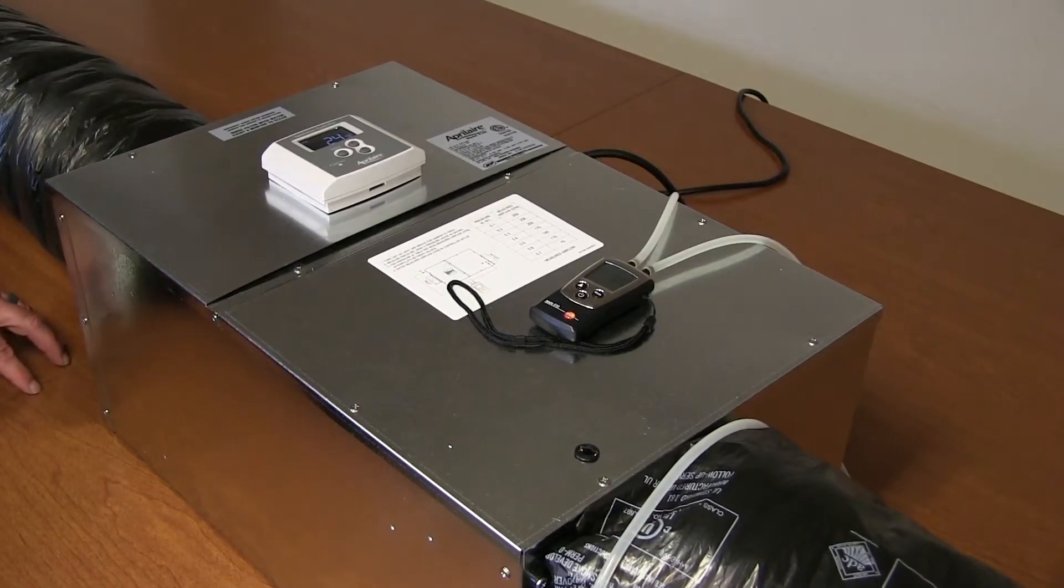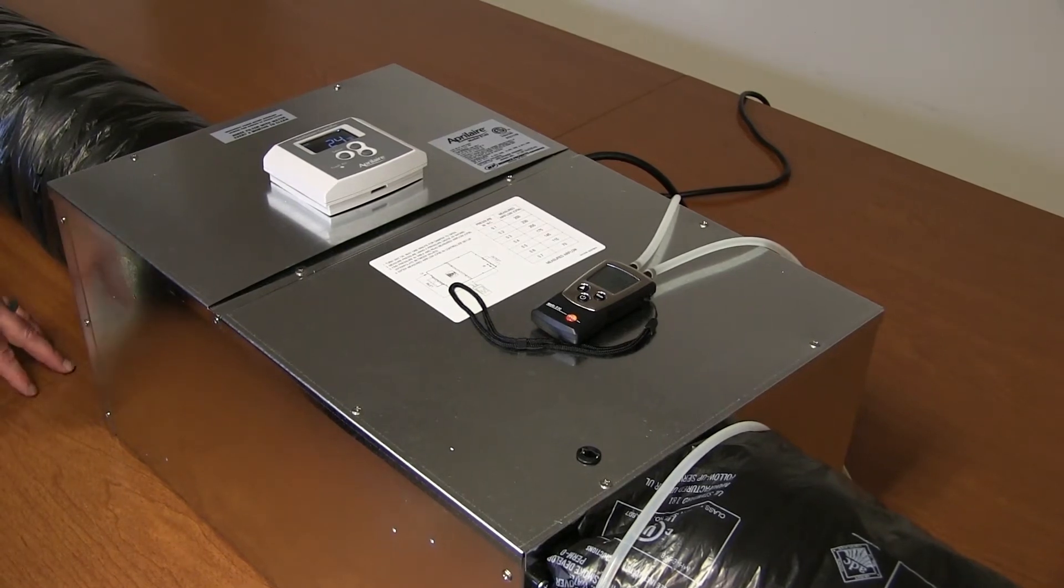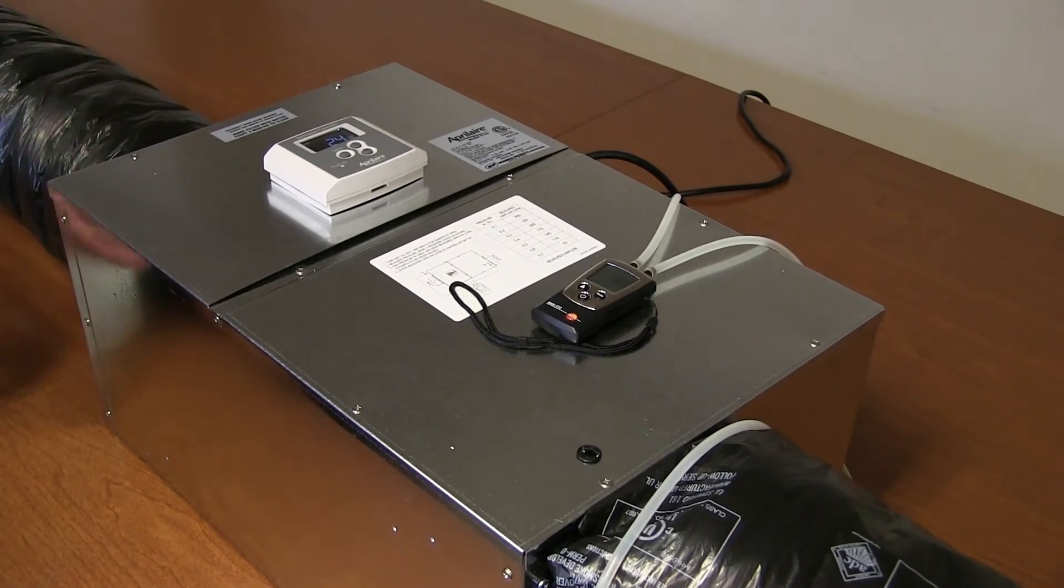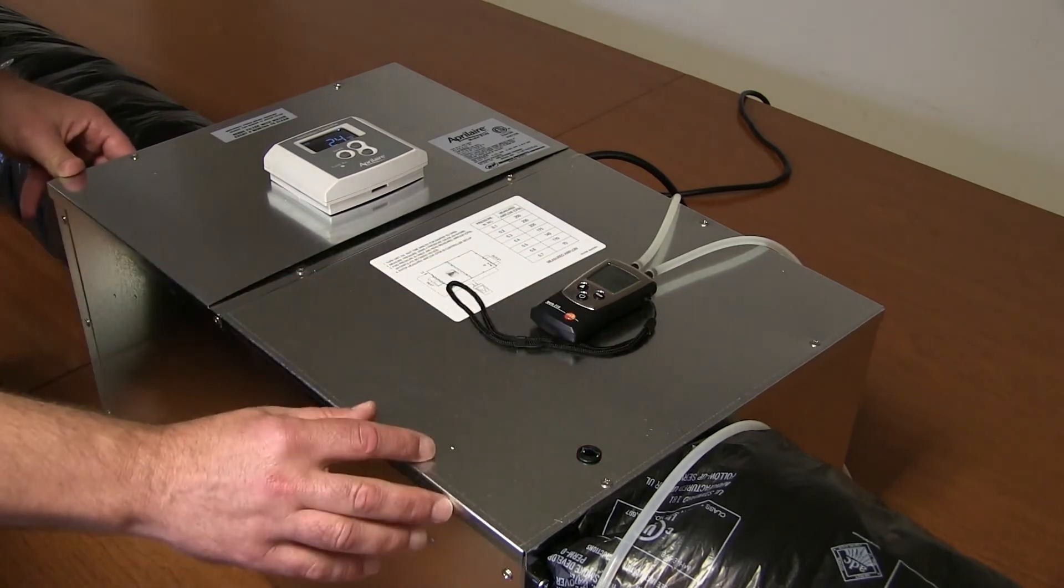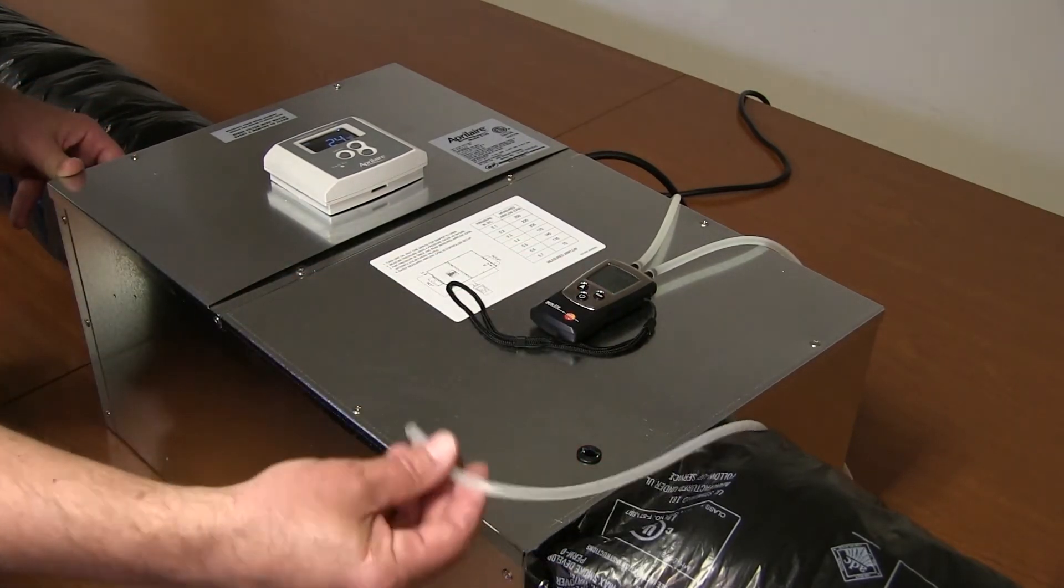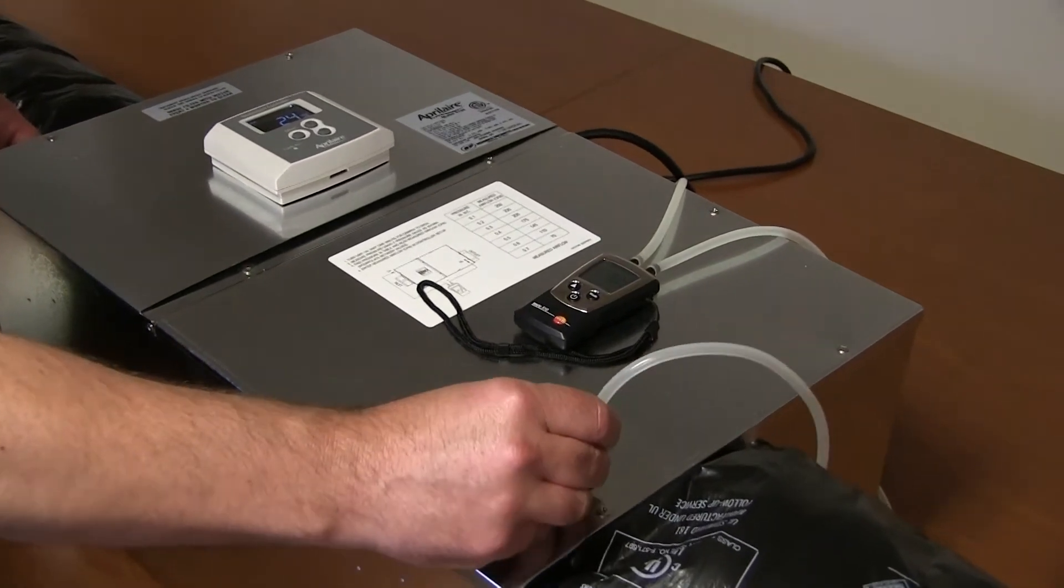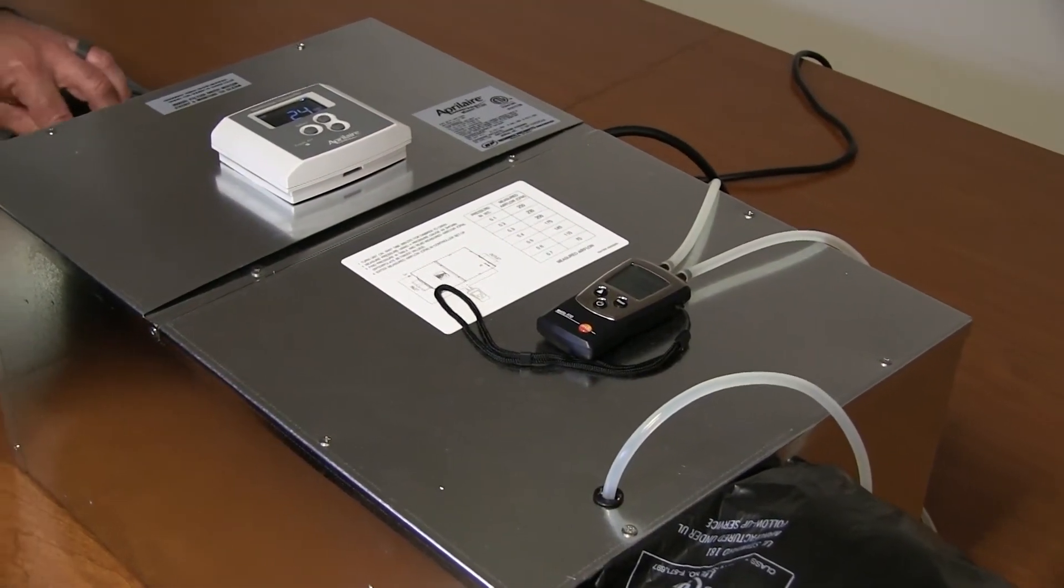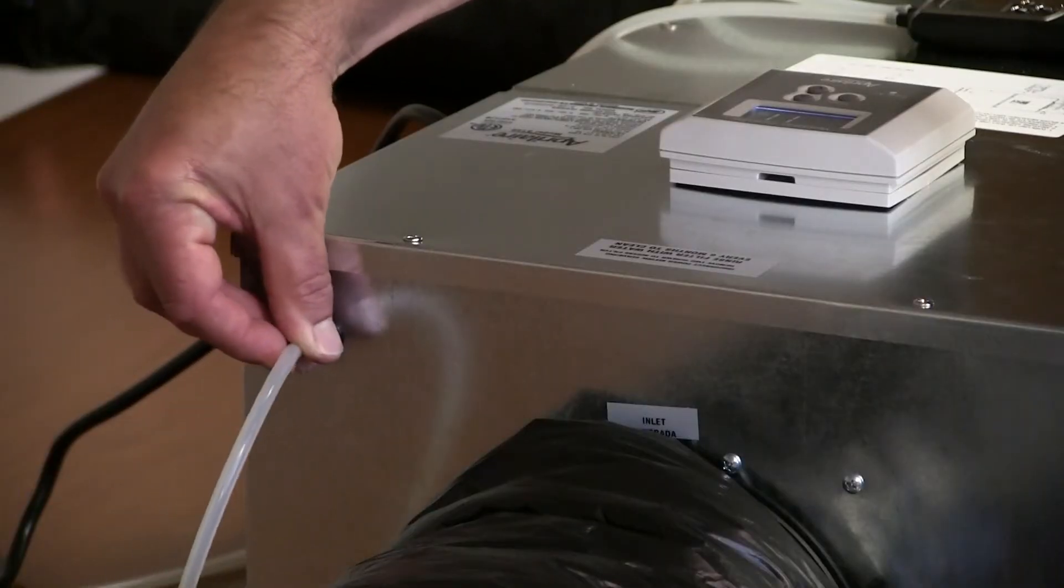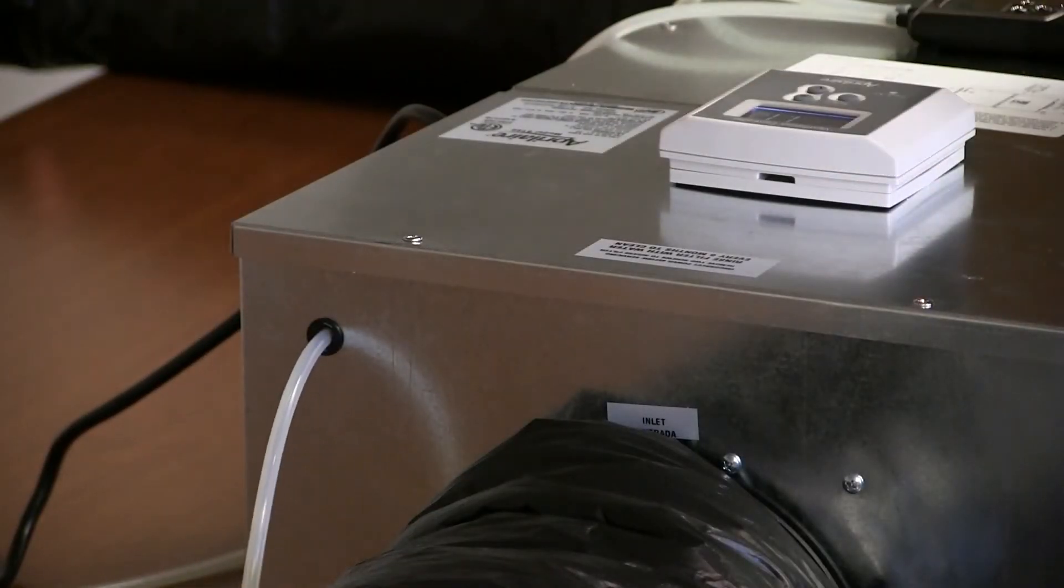All right, so to take airflow measurements with the 8140 after it's been installed is very easy. We're going to use a pressure measuring gauge here, and we're going to take the positive side of the gauge and connect it to the outlet port of the 8140. Then we're going to take the negative side of the pressure gauge and put it to the inlet side port of the 8140.